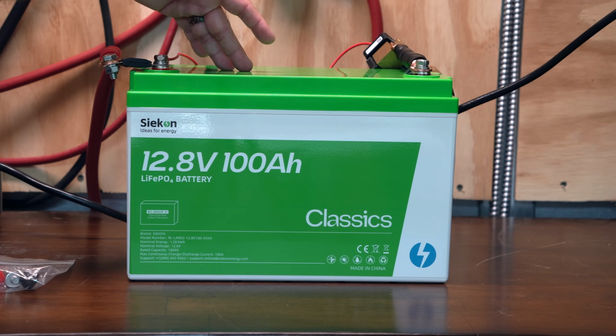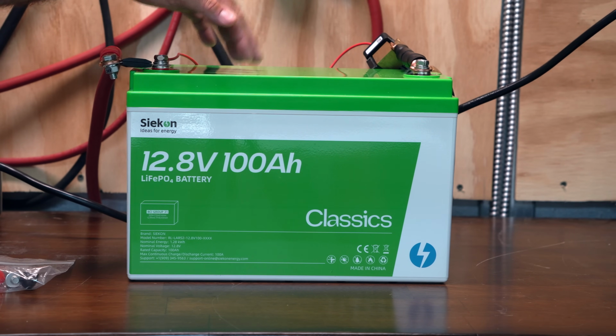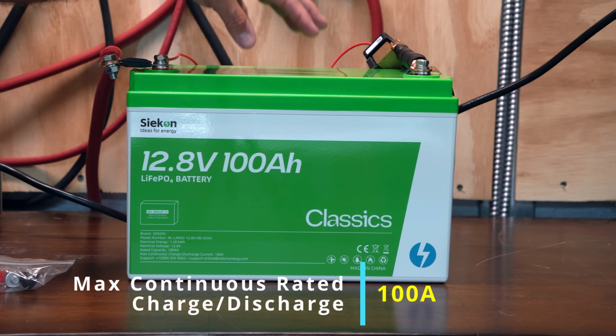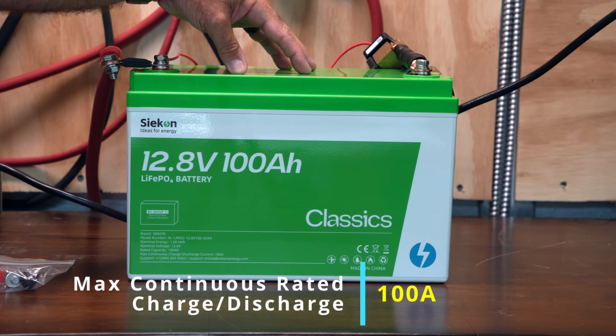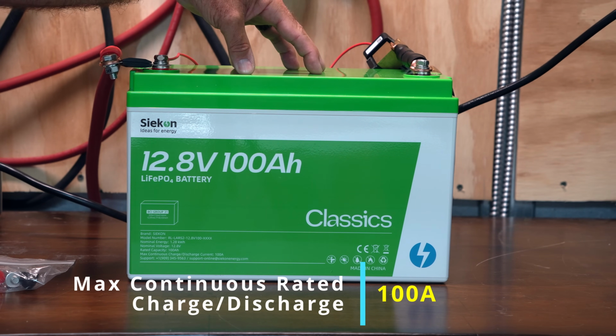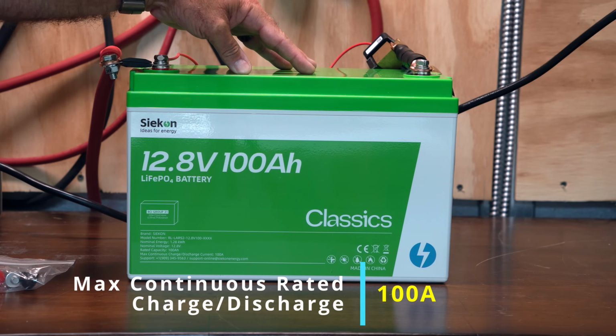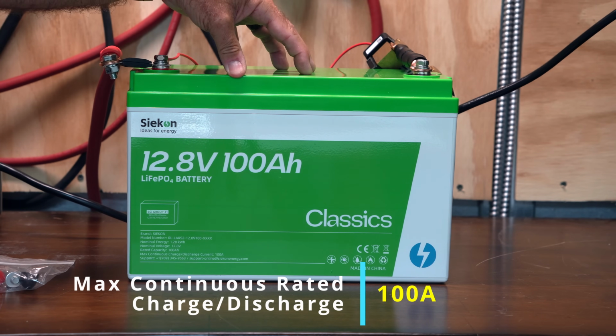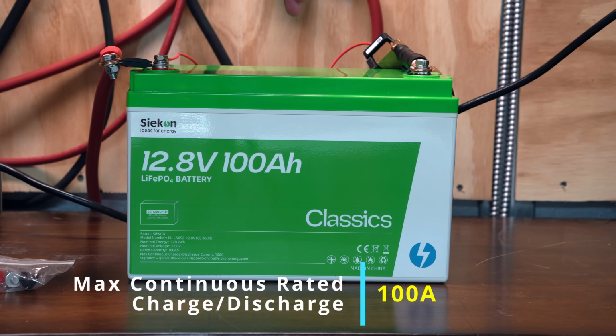Since it is a 100 amp BMS, the maximum continuous discharge and charge rate is rated for 100 amps, although I think we're probably going to be able to get a little bit more than that as a discharge rate. We're going to test that to see if that's the case, and we're also going to make sure it can sustain that 100 amps for a reasonable period of time.